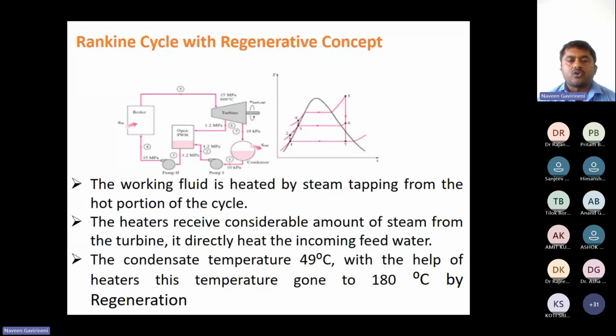We have studied parallel flow, counter flow, and cross flow, right? In our power plants, all heaters are counter flow type heat exchangers. The temperature increase is 10 to 20 degrees. We have four LP heaters. One is LP heater one, immediately at the condensation stage. Later there are three LP heaters after the CEP. There is a pump arrangement after the heaters, that is the condensate extraction pump, which I will show you. There is a practical screenshot, I will show you by that time.